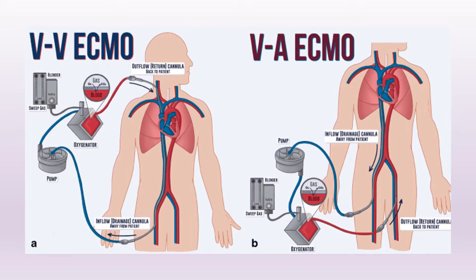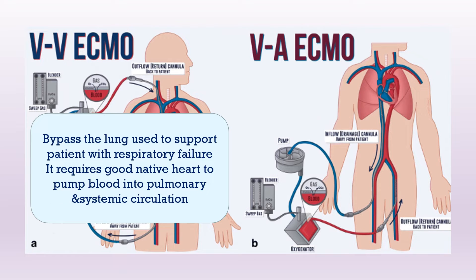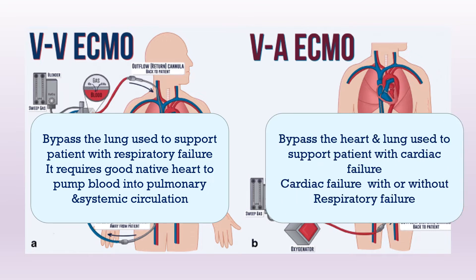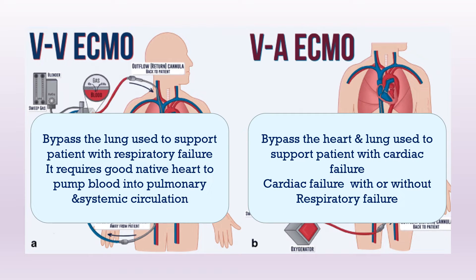There are two types of ECMO: respiratory ECMO or VV ECMO, and cardiac ECMO or VA ECMO. VV ECMO is used to bypass the lung and can support patients with respiratory failure; it requires a good native heart to pump blood into pulmonary and systemic circulation. VA ECMO bypasses both the heart and the lung, used to support patients with cardiac failure, with or without respiratory failure.